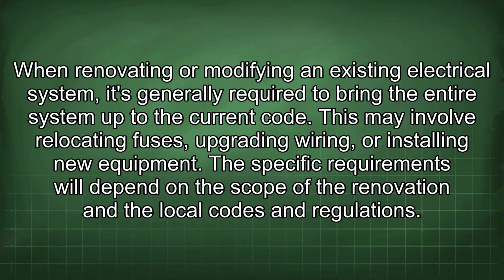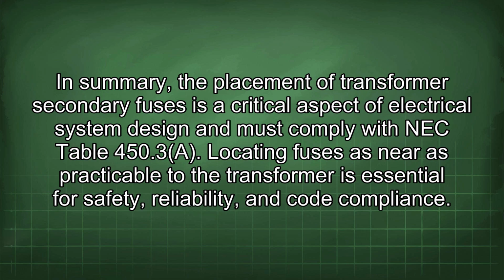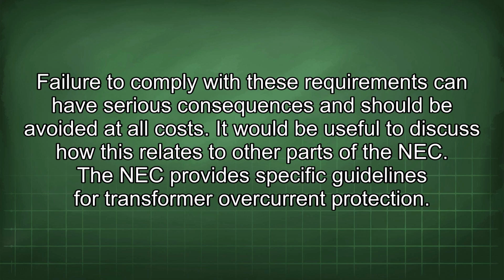It's important to stay up to date with the latest code requirements and to ensure that your electrical system is compliant. When renovating or modifying an existing electrical system, it's generally required to bring the entire system up to the current code. This may involve relocating fuses, upgrading wiring, or installing new equipment. The specific requirements will depend on the scope of the renovation and the local codes and regulations. In summary, the placement of transformer secondary fuses is a critical aspect of electrical system design and must comply with NEC Table 450.3(A). Locating fuses as near as practicable to the transformer is essential for safety, reliability, and code compliance. Failure to comply with these requirements can have serious consequences and should be avoided at all costs.